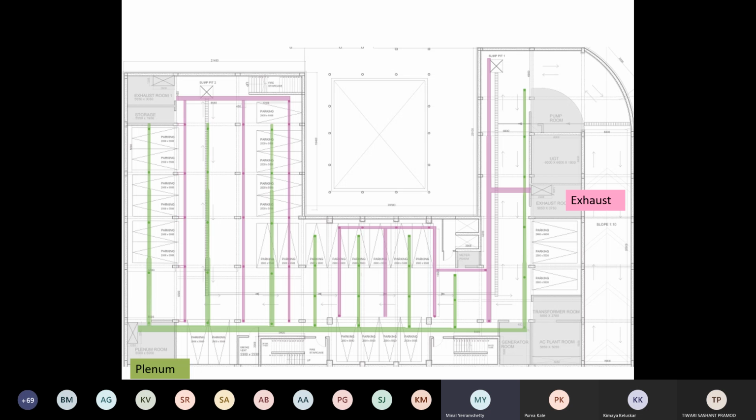A1 का तो छोटा सा volume है ना, because it is only catering to that bay. But as it goes ahead, it starts accumulating the various volumes required by each bay. And that is how the calculation is done. That is why, as you go further from the source of air, the duct size decreases. It helps me, first of all, with costing: the lesser the material spent, the smaller the size, the better the costing. And secondly, which is primarily important to me as an architect, it gives me more headroom.